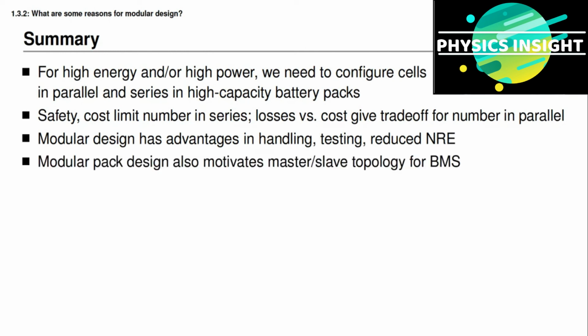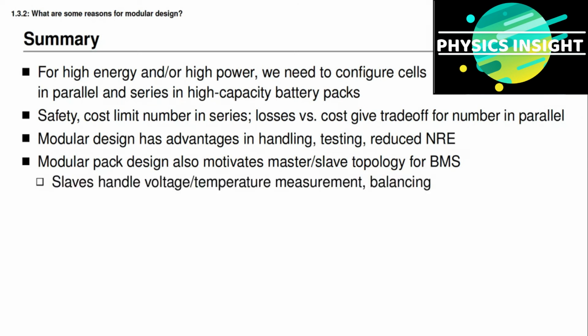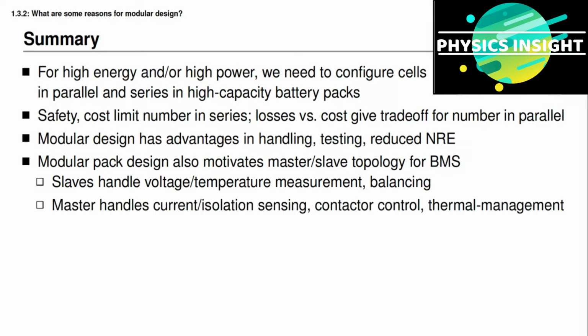The modular design of battery packs motivates building battery management systems with a modular design also, and it's very common to see a master-slave topology. The slaves handle voltage measurement, temperature measurement, and balancing, while the master handles battery pack current sensing, isolation sensing, contactor control, and thermal management.